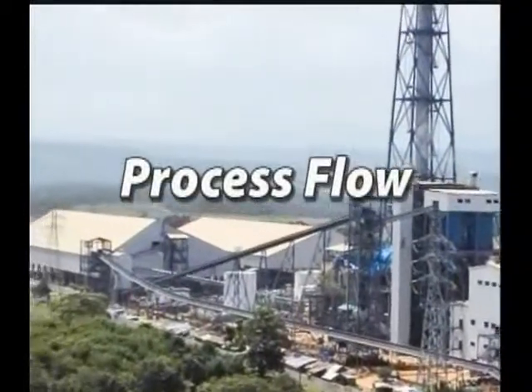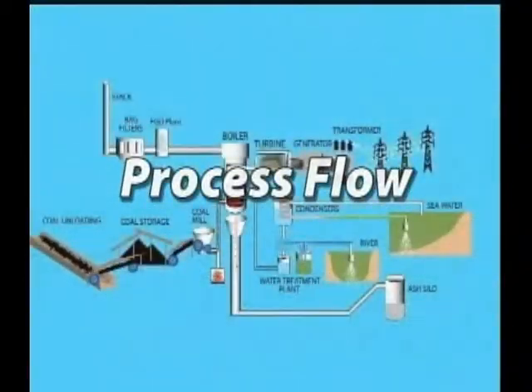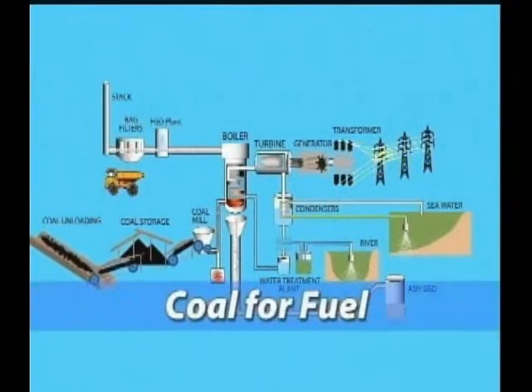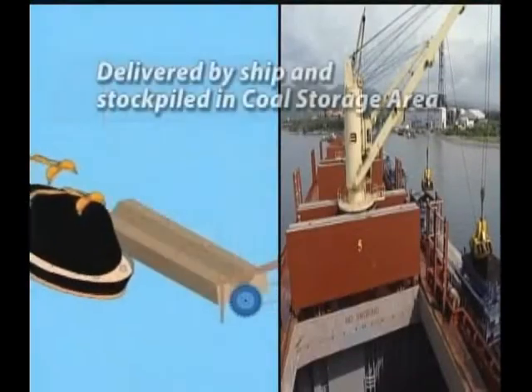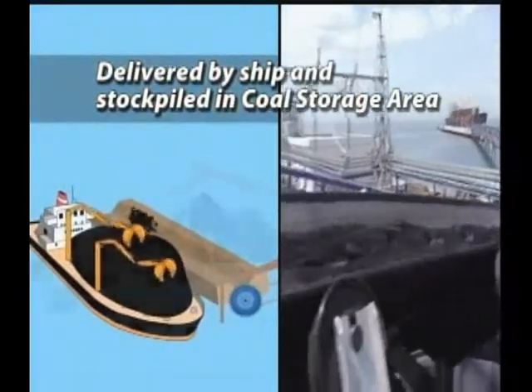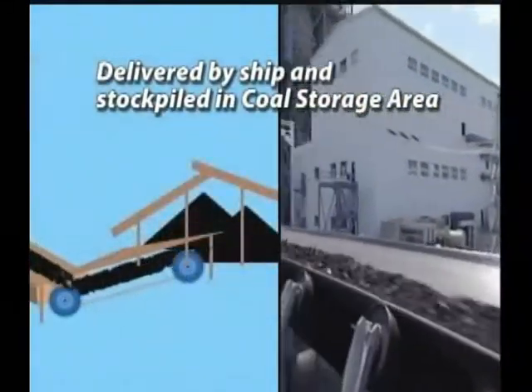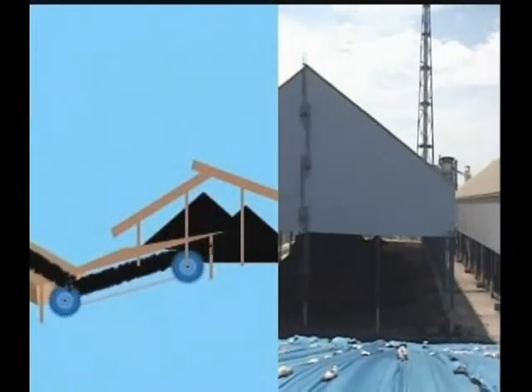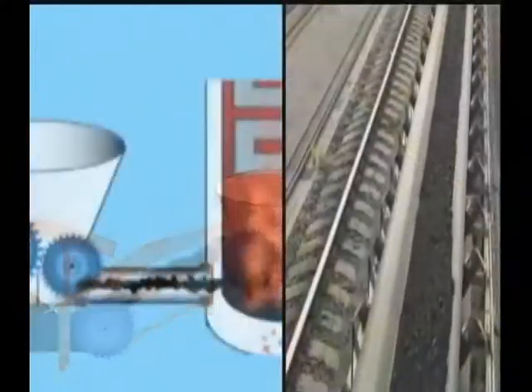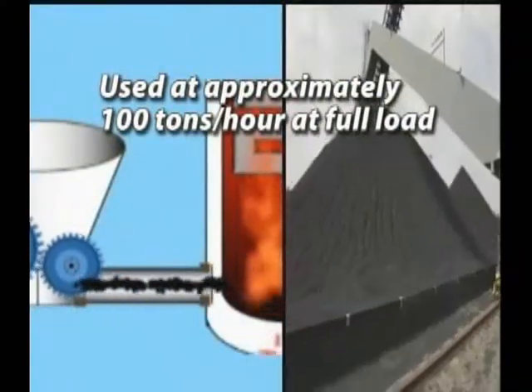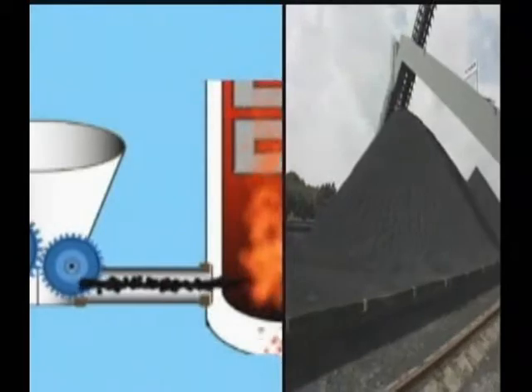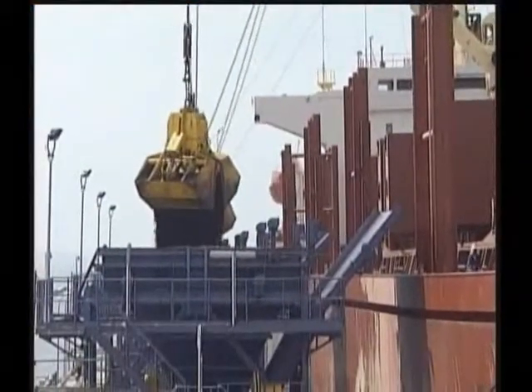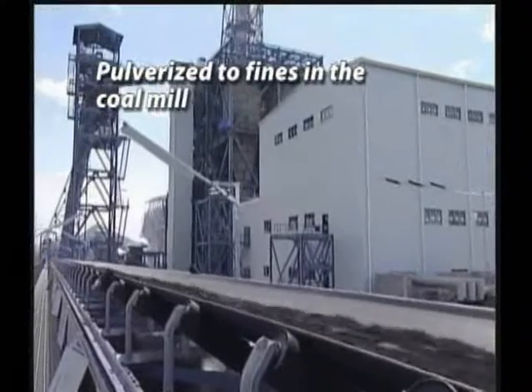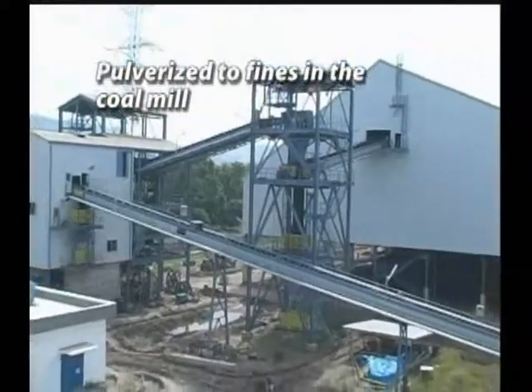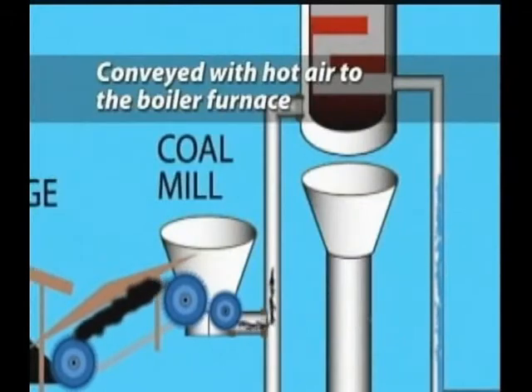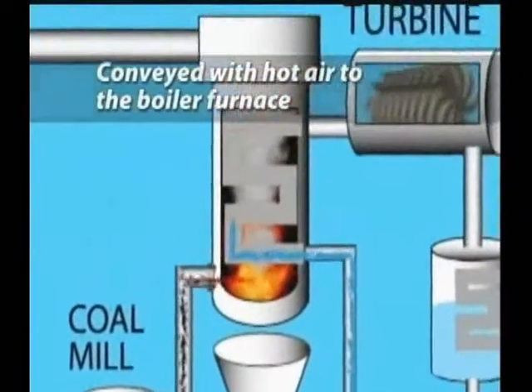Mindanao 210 megawatt coal-fired power plant process flow. Coal for fuel. Coal is delivered to the power plant by ship and stockpiled in a covered coal storage area with a maximum capacity of 160,000 tons. Coal will be fired at a rate of approximately 100 tons per hour at full load. Coal is delivered in its natural mineral form and must be pulverized in the coal mill. The pulverized coal is conveyed together with hot air to the boiler furnace where combustion takes place.